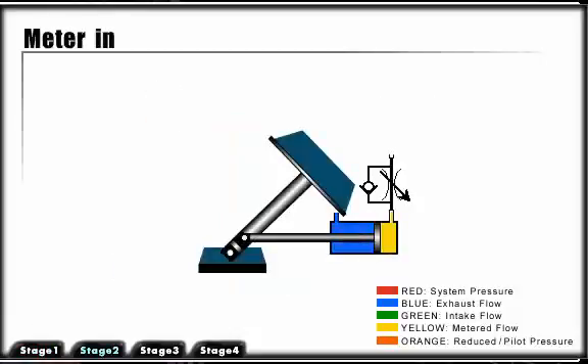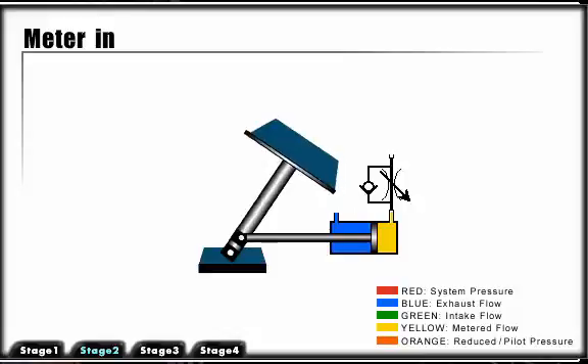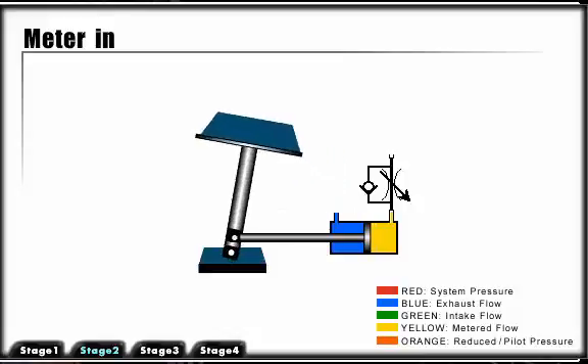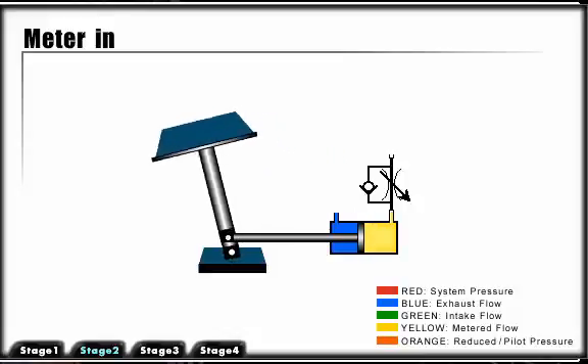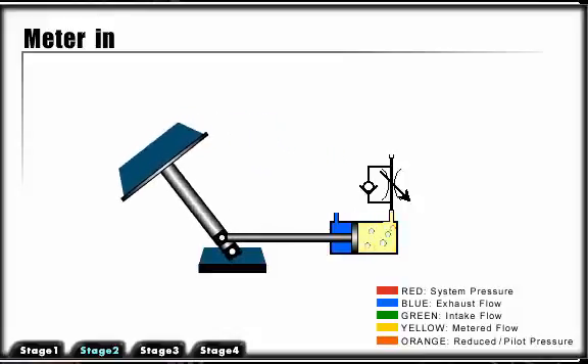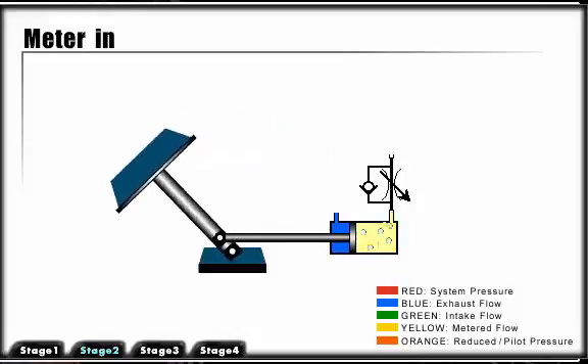The advantage to meter in is that it is very accurate with a positive load. However, when the load goes over-center, the load becomes negative or overrunning. The load is no longer being controlled by the cylinder. As the load overruns, it causes the cylinder to cavitate.